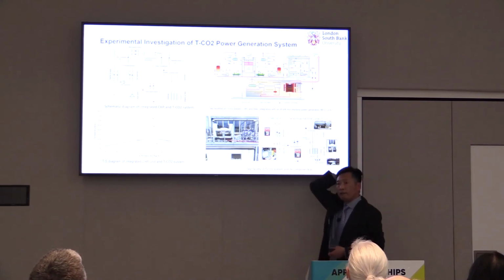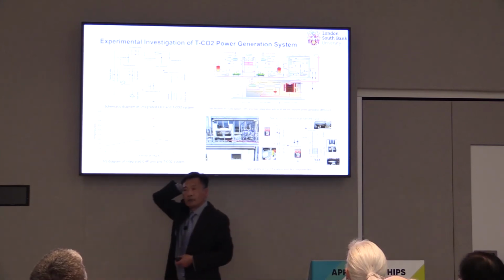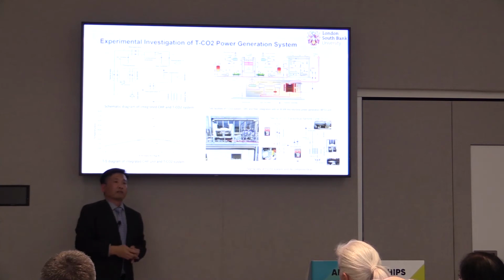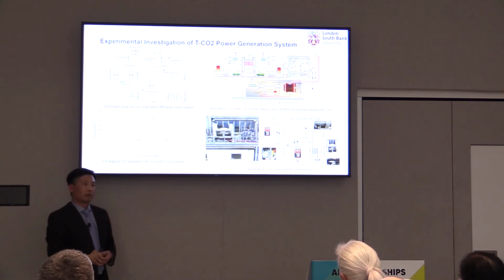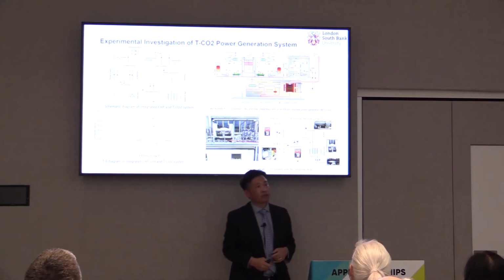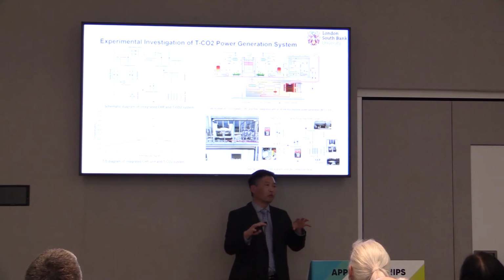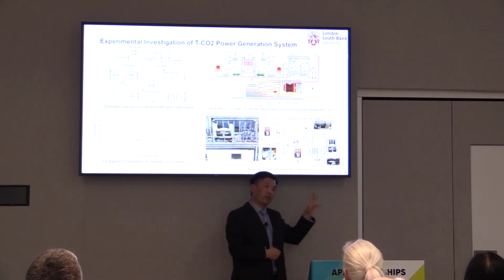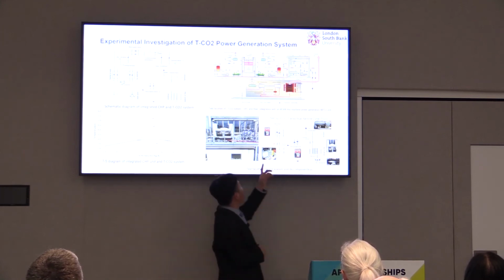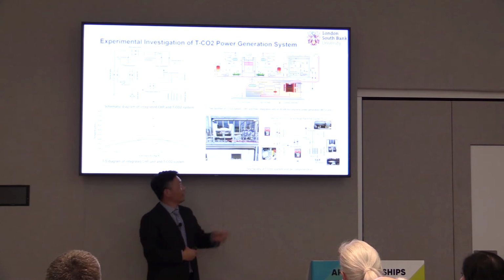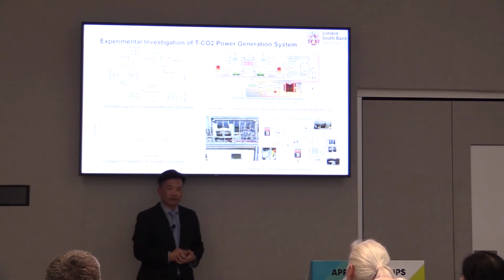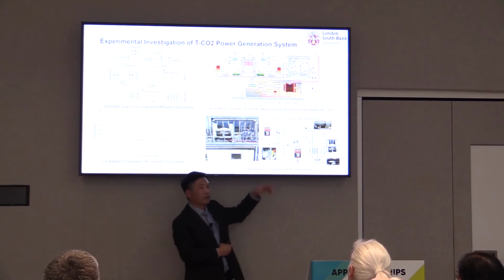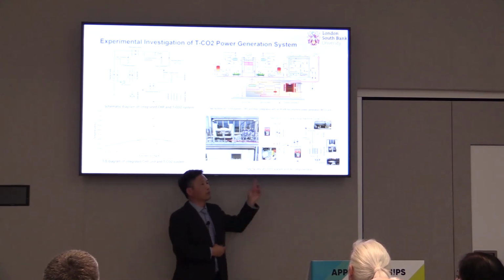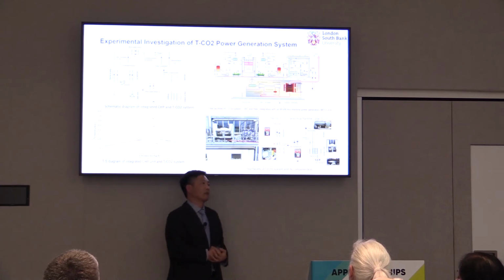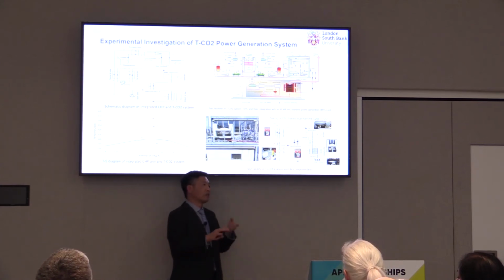So I think what we did, we were nearly the first who developed this test rig for the tri-generation transcritical CO2 cycle, and this turbine, actually not many, I think in the world only one manufacturer from France manufactures this CO2 turbine and the CO2 pump. This is not particularly for the transcritical CO2 system, so we found a lot of leakage because this is not the first time to be used in this transcritical CO2 system. So we found a lot of issues for that.